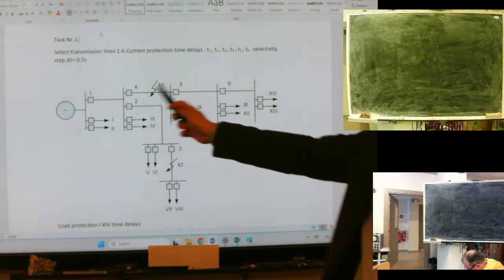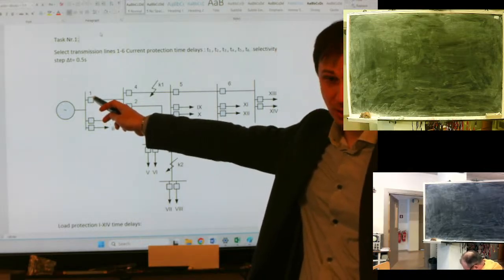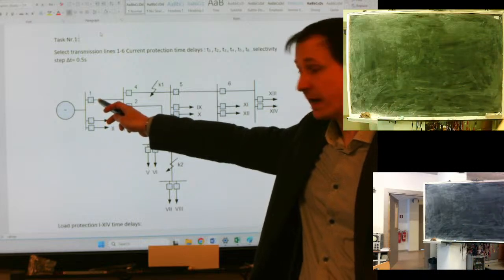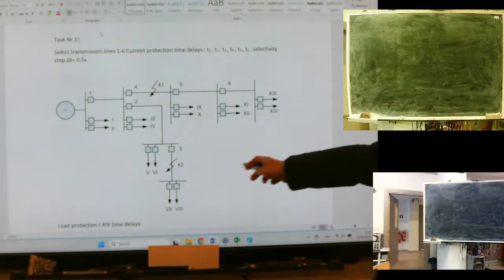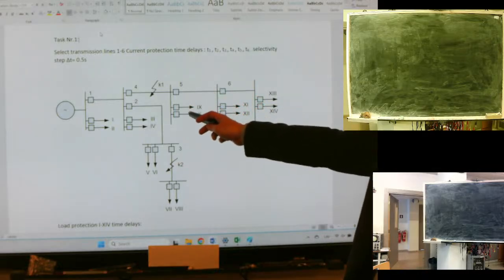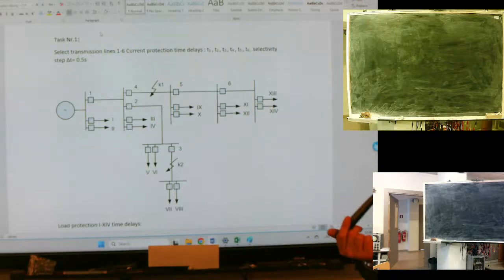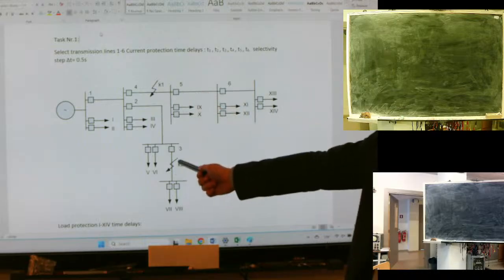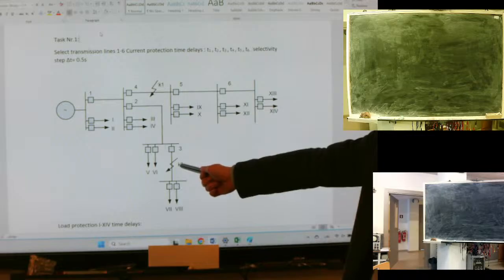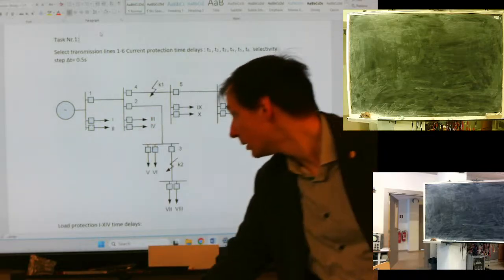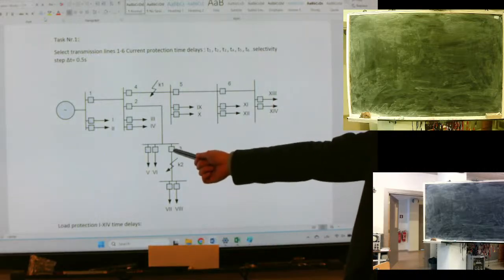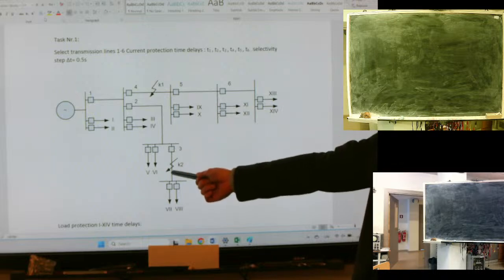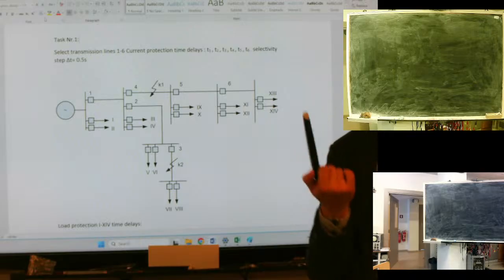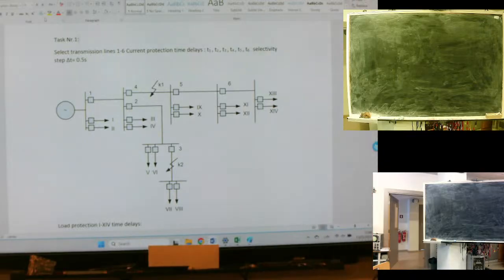In case we have a fault anywhere and we disconnect power switch number 1, located on line number 1, almost every load will be without electricity, disconnected from the network. Is it good? No. For example, if we have a fault here at T2, why do we need to disconnect line 1? It is enough to disconnect power switch number 3 to isolate the fault from the grid. So what is the idea of our protection? Because the very first question for the protection design is who we are protecting.